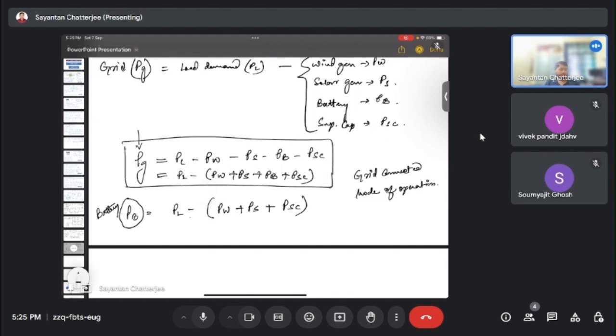The problem is that this mismatch needs to be handled even in islanded mode of operation. It should be assured that the battery value stays within a proper range, because the state of charge, SOC, is generally maintained between 10 and 90 percent. Beyond 90 percent is not kept, and below 10 percent is also not kept, in order to maintain proper battery life.